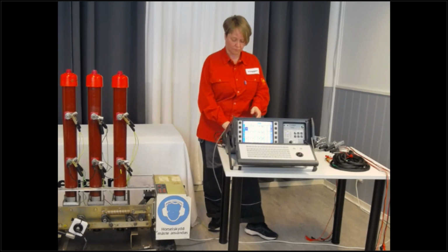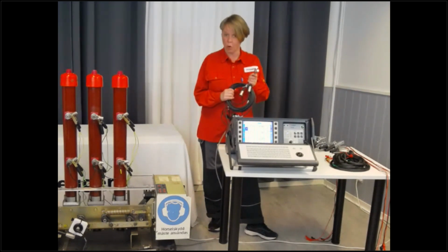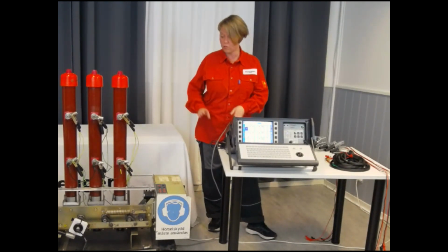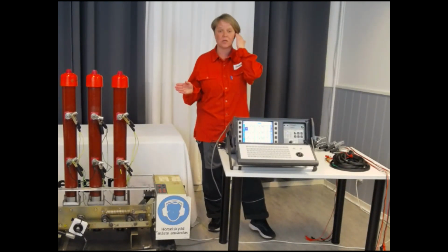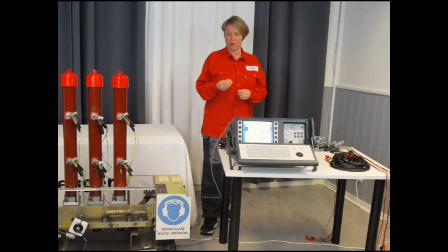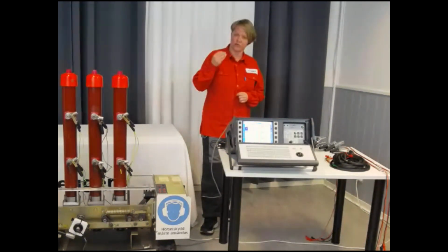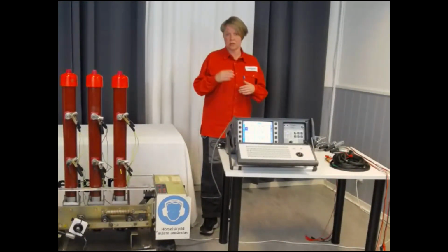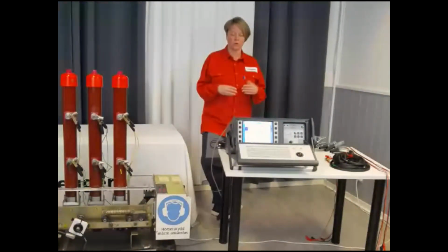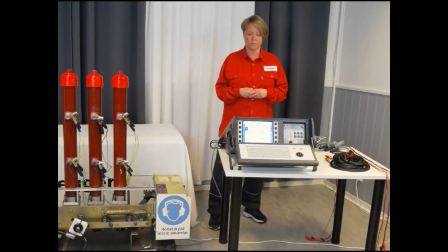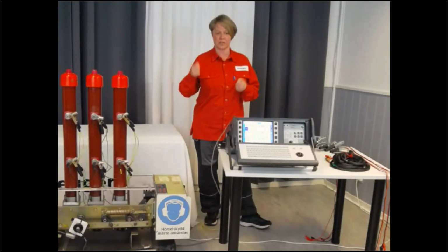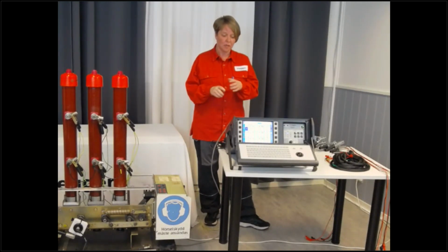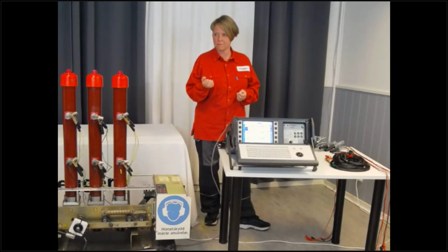DCM is a module, so it's not always included. And the ferrites are not always included, because normally you don't need them on the outdoor breakers. So it's like an accessory for the dual ground on the GIS. But sometimes in extreme cases, you could use them also on normal outdoor objects. But preferably I would use a separate grounding device, as I recommended in the beginning.